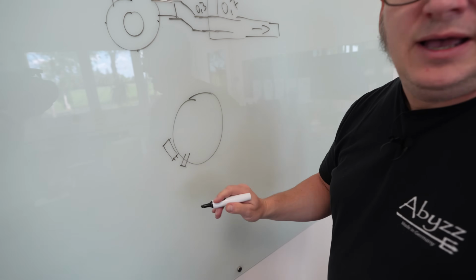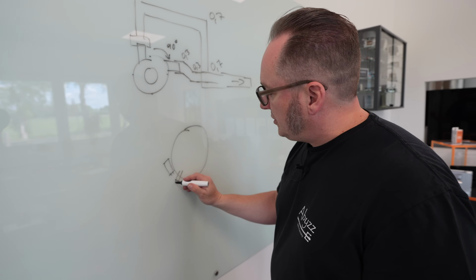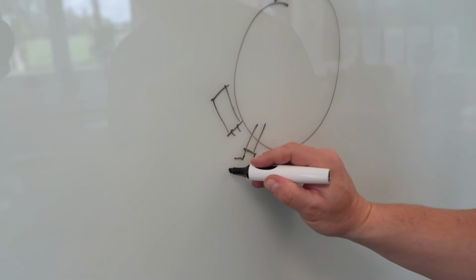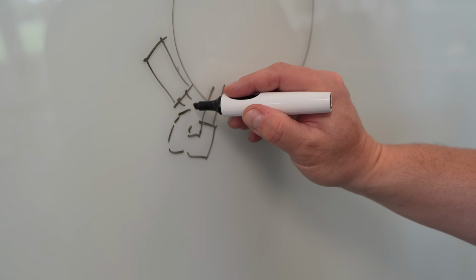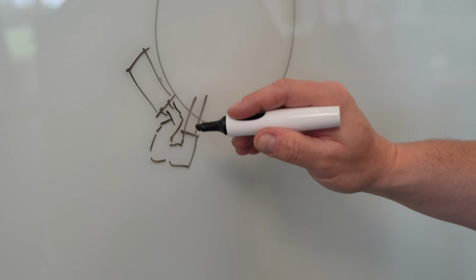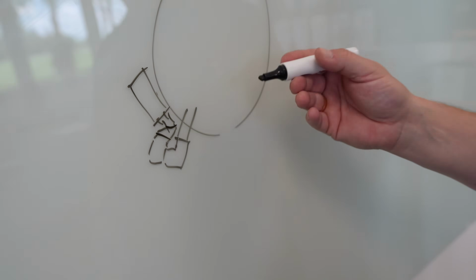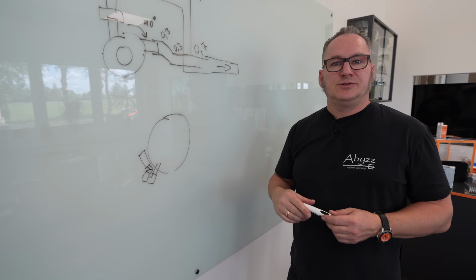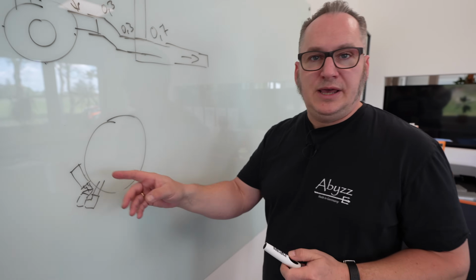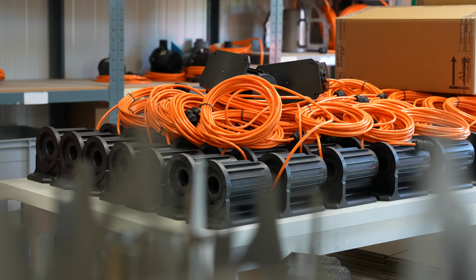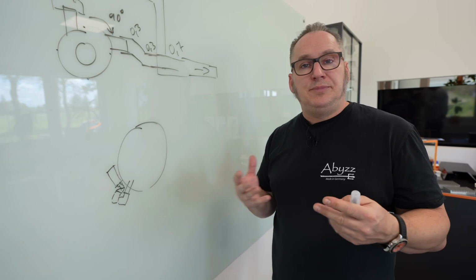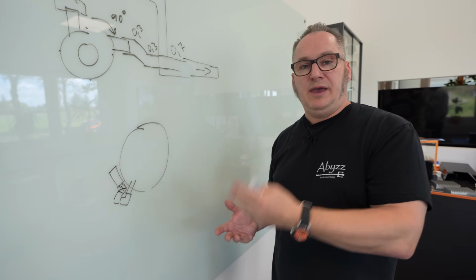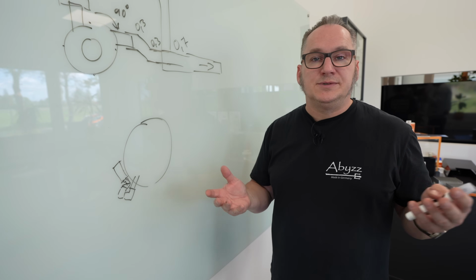What happens, and I actually have that as a picture, is the connection goes in, a 90 degree comes out, another 90 degree goes in, and then a 45 degree, and then another weird construction. So you end up having 3 or 4 different angles in this construction. There's no straight intake into the pump. Our pumps are not self-priming, so they cannot create a high underpressure on air. That's for a reason, because an impeller wheel can't be as efficient with air as it is with water, because the viscosity of those two mediums is completely different.